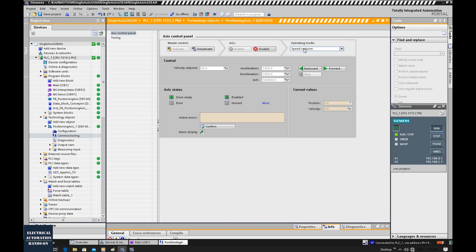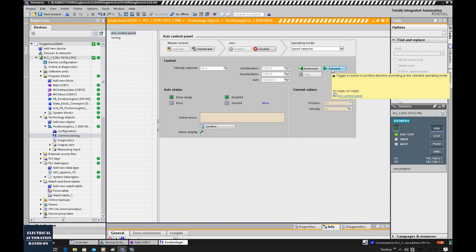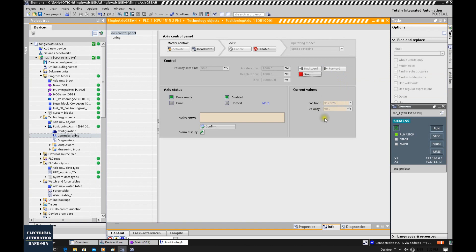We can set the speed here and enable the axis. If this axis is connecting one actual servo drive, after this enable you will hear that motion drive will be energized. Then we can select this speed setpoint, and the speed will follow this setpoint. Once we click this forward, our axis will start to run. For example, click this forward. We will see the system will start to run based on our setpoint.